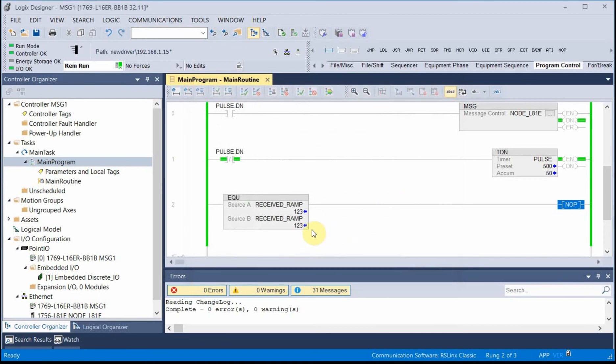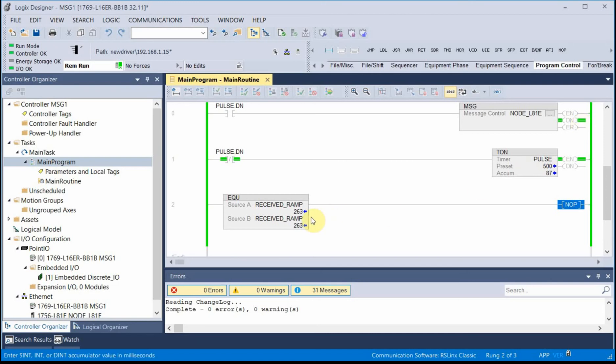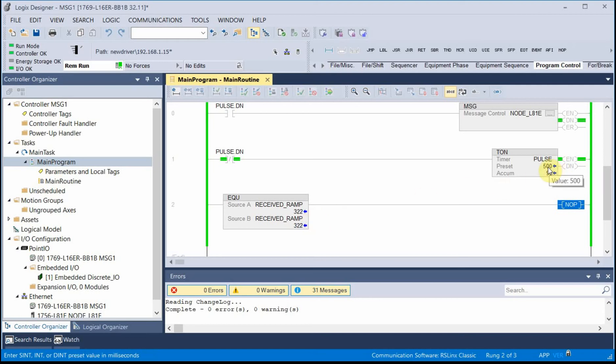So as I look at it, I can see a lot of things going on. The pulse is running. My message instruction is done constantly because it's happening very quickly. I'm reading in a ramp value, but you see how it's not incrementing evenly. That's because the pulse is kind of slow. Let's change it to 100 milliseconds.